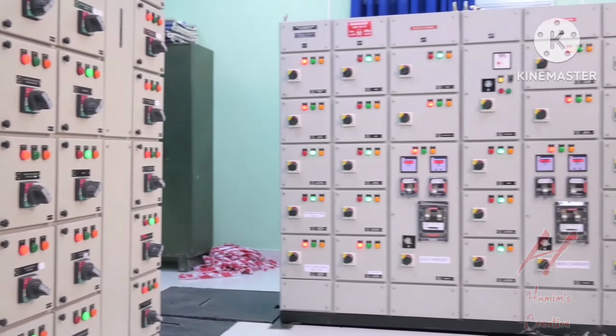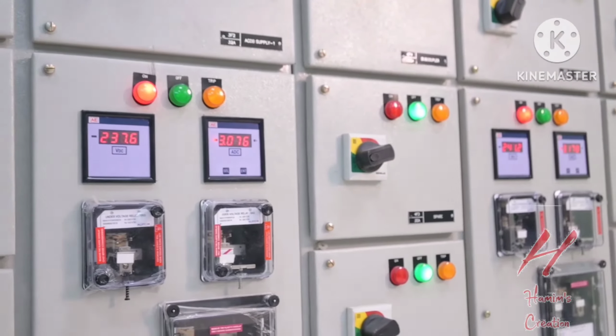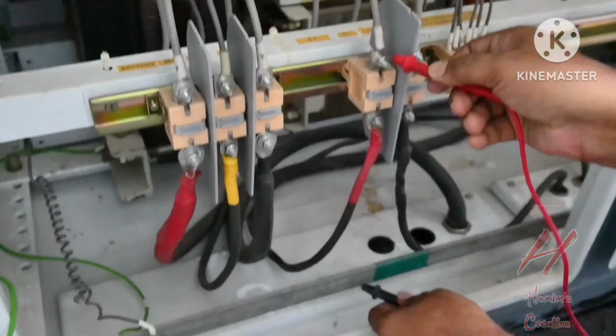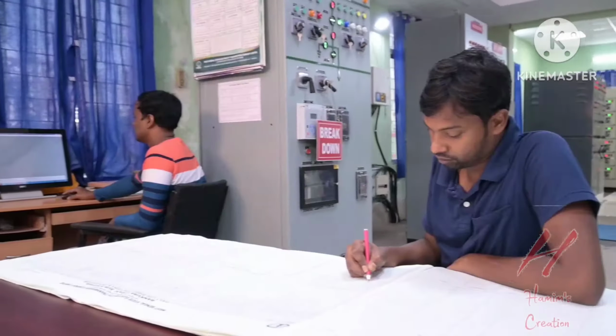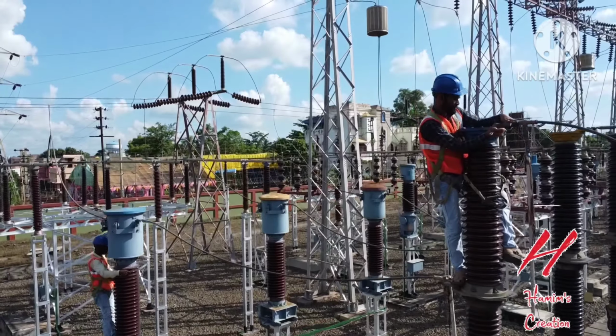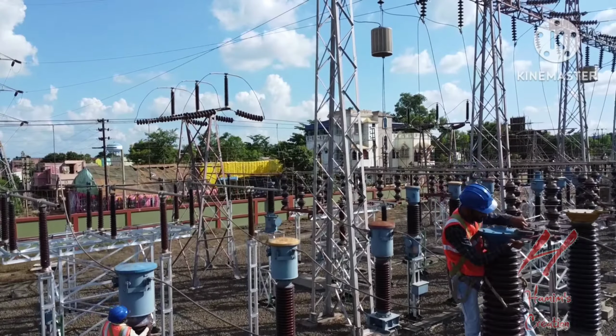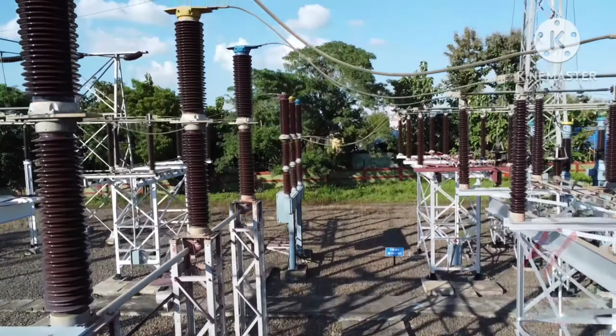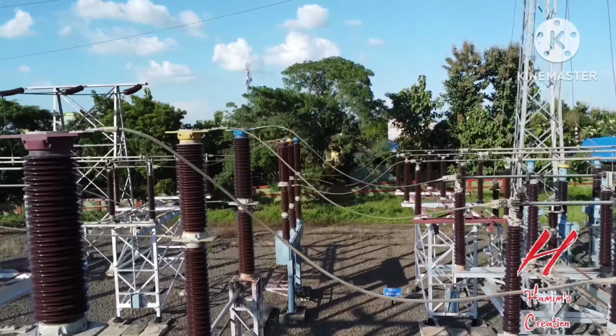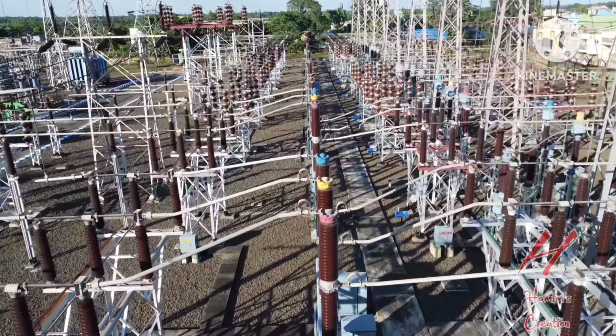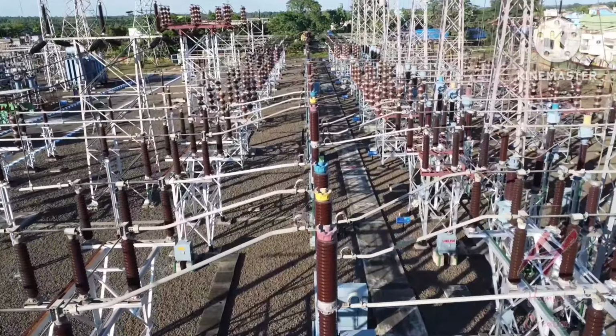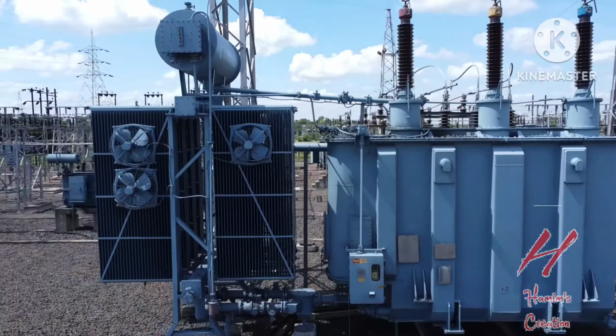The entire DC system has been maintained very well with double set battery and charger. Checking of earth fault, if any, has been done regularly. Condition-based monitoring has been done as per maintenance schedule to minimize operation and maintenance cost to avoid forced shutdown.